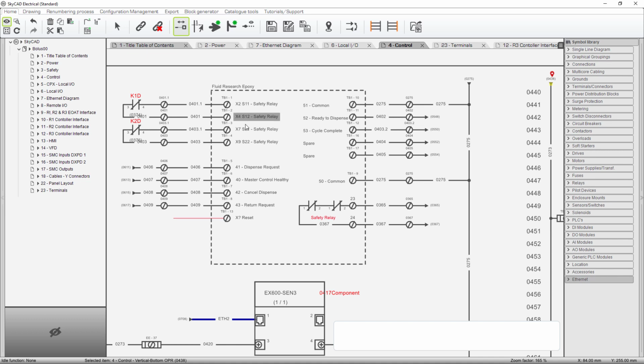To do that, this epoxy system has 4 terminals that we can interface 2 channels of our safety programmable relay into its safety circuit. So these would have jumpers across them. So you would have this terminal jumper to this one, and then this terminal jumper to that one if you had no external e-stop stuff. Okay? So you could say this is where you would hook an external e-stop, 2 channels. This is a single connection going back to the main panel safety circuit.